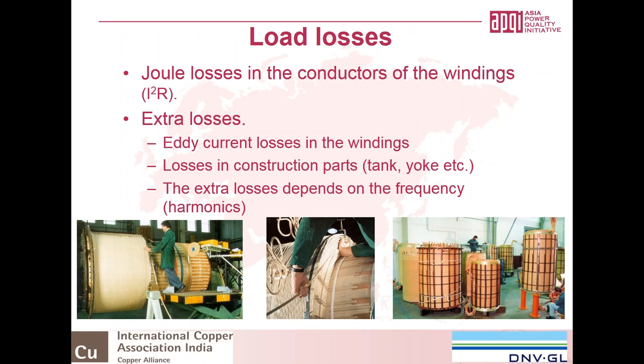Mainly the extra losses within transformers heavily depend on the frequency. For the eddy currents within windings, it's normally the square of the frequency, and if you talk about construction parts in the transformers, you will often see that they scale with the frequency to the power of 0.8.